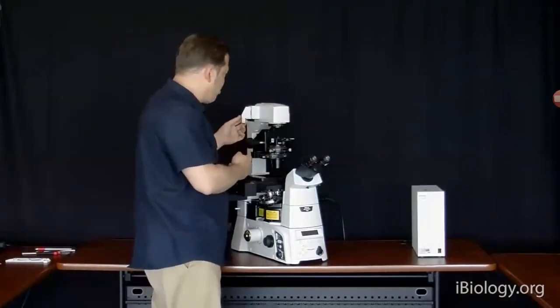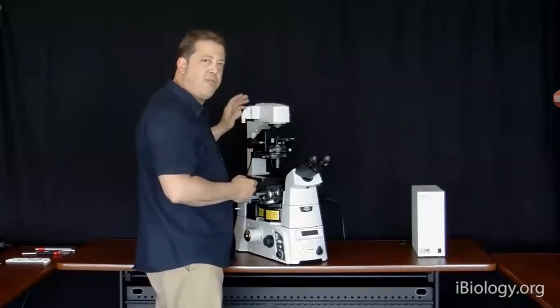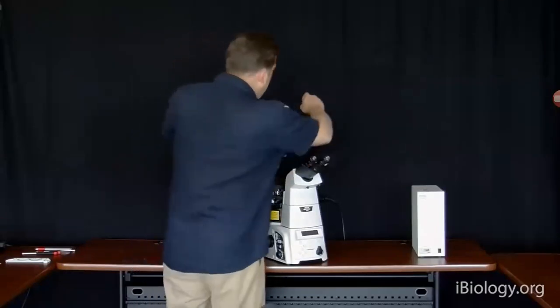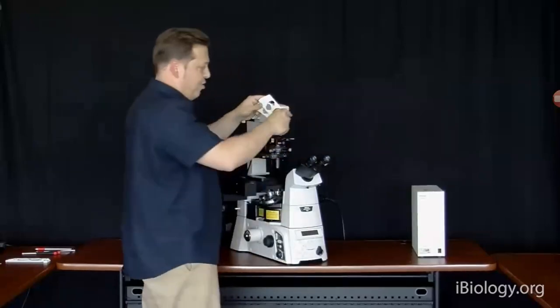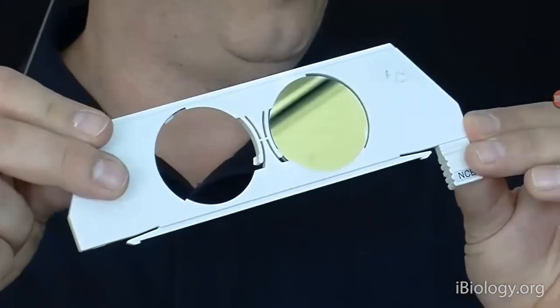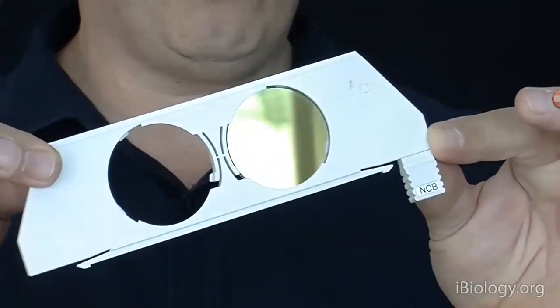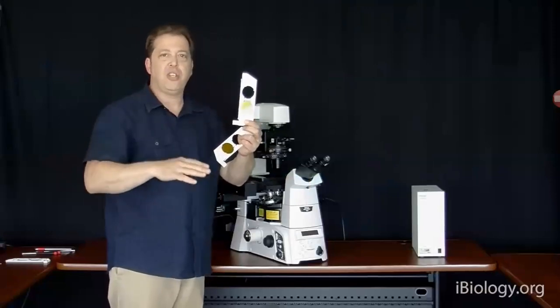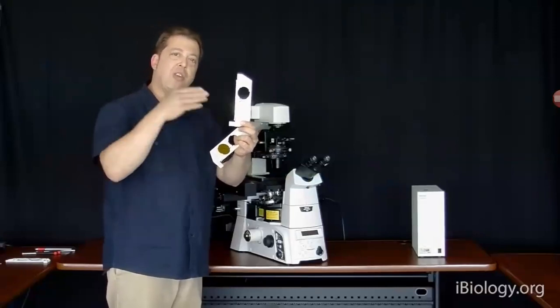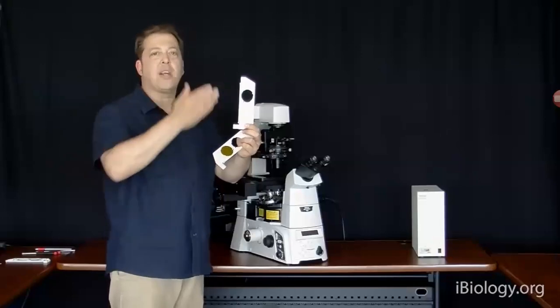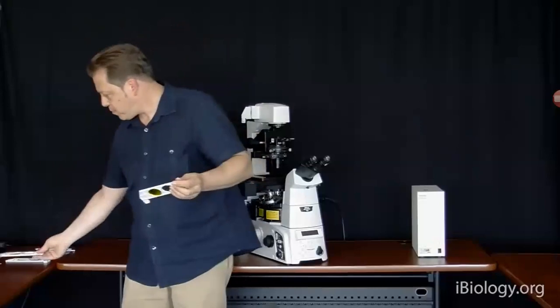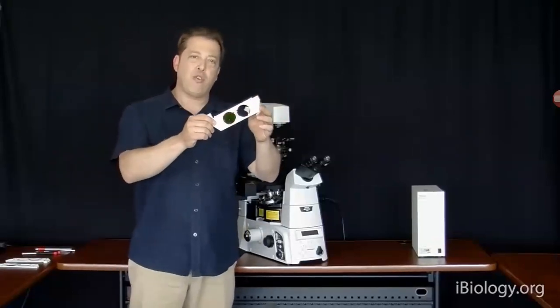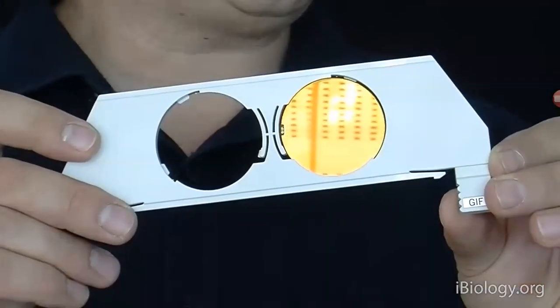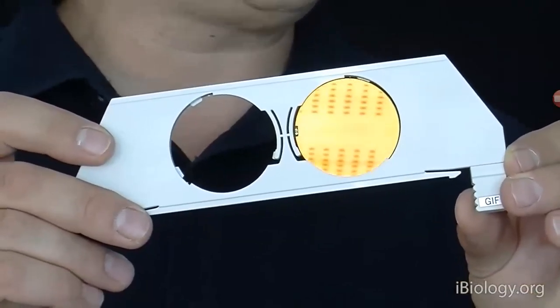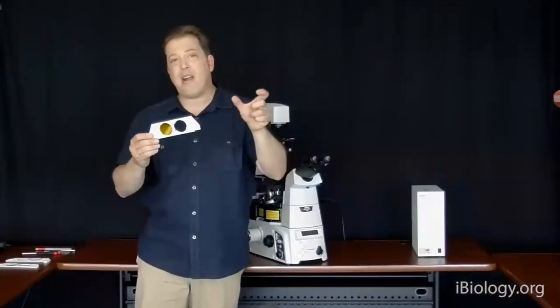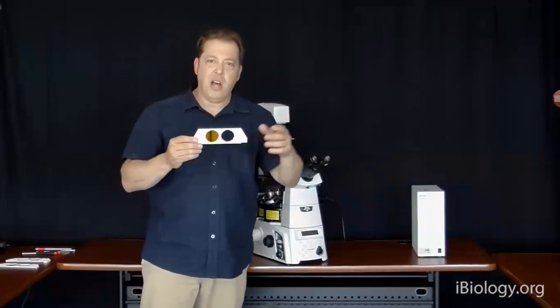Then we have several filter holders. There's an auxiliary holder that holds a neutral density filter. We can also use this to hold an infrared cut filter for our dynamic focusing system, the perfect focus, which we'll talk about later. And then on this side of the microscope, we have two other filters. This one is called an NCB11 neutral color balancing filter. It actually looks blue when you look through it. What that does is, when the halogen bulb runs at low voltage, it is more reddish, more orangish in color, and the neutral color balancing filter will give you a white background as if you're running the bulb at higher voltage when it puts out more white light. And then we have a green interference filter, which is a narrowband green filter that is used for contrasting techniques like differential interference contrast or phase contrast to give you sharper images, sharper resolution in those contrasting techniques by narrowing the band of wavelengths that you're using to illuminate your specimen.